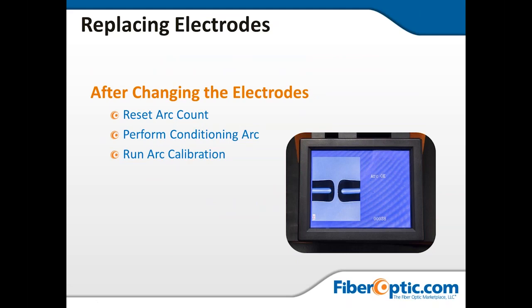Replacing electrodes. After changing the electrodes, reset the arc count, perform conditioning arc or stabilization, and then you will be running an arc calibration. This will have to be done numerous times until the splicer is acclimated to where you're working. If you're outside and it's cold, it may take a little longer. If you're inside and there's a lot of dirt, that can cause more arc calibrations to have to be done.